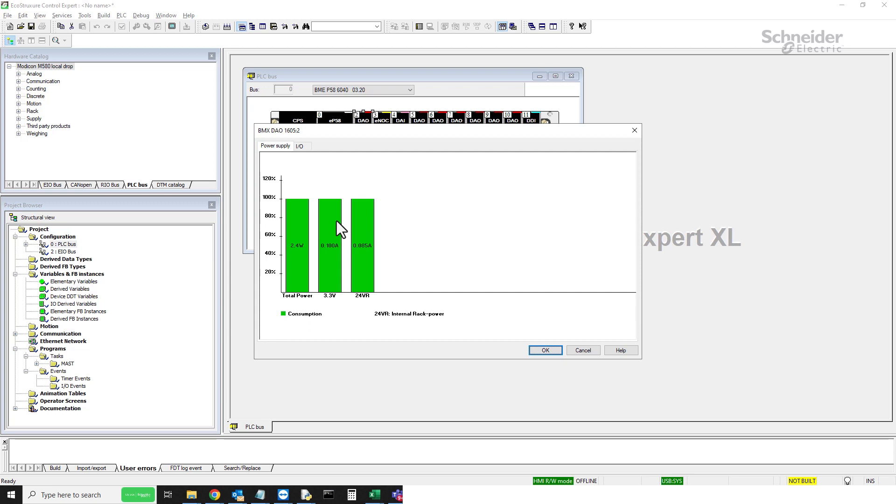It's always a good idea to keep your architecture power consumption well below the 100% threshold. That way, if there is any inrush current or anything like that, the power supply will not be overstressed. This also prolongs and helps with the lifespan of the unit as well.